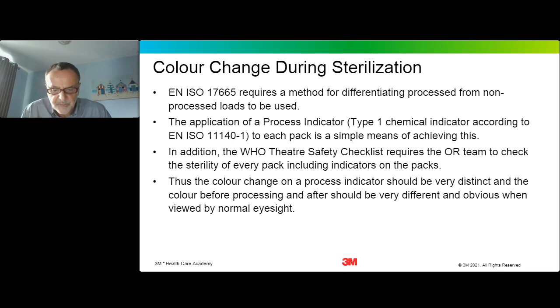So let's consider the colour change during sterilisation. Now, one of the popular misconceptions is that autoclave tape or any chemical indicator-based product will suddenly change colour when it's exposed to a certain temperature for a certain length of time. Well, this is not really true. These indicator tapes don't act like a light switch, where one minute the light's on and then immediately you turn it off, you get a dark colour. The colour change will actually occur gradually and at a speed which is dependent on the temperature of exposure. So the higher the temperature, the quicker the ink changes to its final colour. But that colour change is not instantaneous.